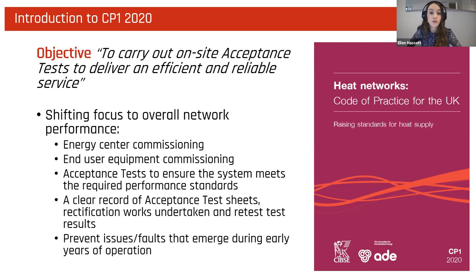Poor commissioning and performance of endpoints, such as heat interface units or fan coil units, is often associated with elevated flow rates and return temperatures, where a few poorly performing units can have a detrimental effect on the heat network's performance and efficiency. Acceptance testing provides performance verification of the energy center and all the endpoints, which Freddie and I will delve into further. Feedback is then provided to contractors for rectification. This process ensures installation, commissioning, and operation are all as per design and performance specification, and prevents issues and faults emerging during the early years of operation, where their rectification would be more expensive and more intrusive.